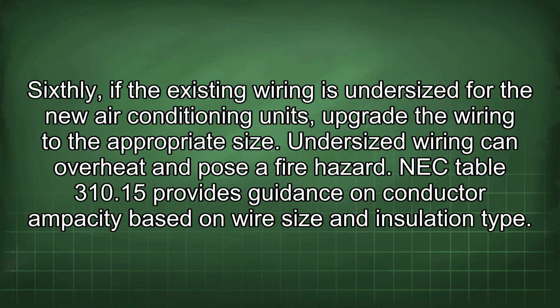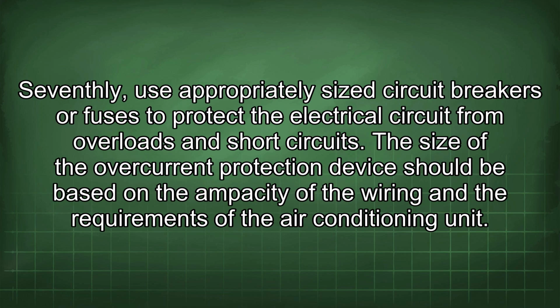Sixthly, if the existing wiring is undersized for the new air conditioning units, upgrade the wiring to the appropriate size. Undersized wiring can overheat and pose a fire hazard. NEC Table 310.15 provides guidance on conductor ampacity based on wire size and insulation type. Seventhly, use appropriately sized circuit breakers or fuses to protect the electrical circuit from overload and short circuits. The size of the overcurrent protection device should be based on the ampacity of the wiring and the requirements of the air conditioning unit.